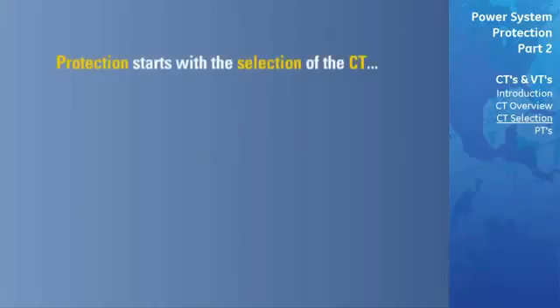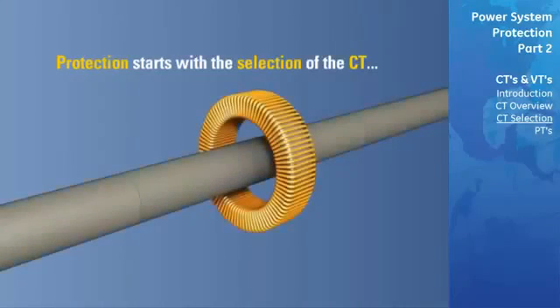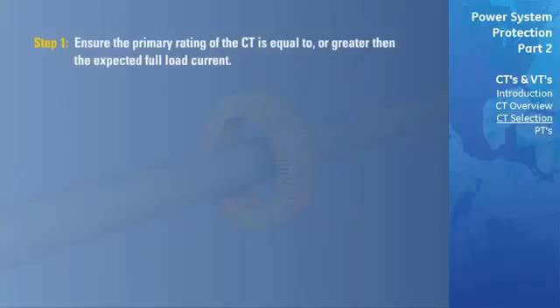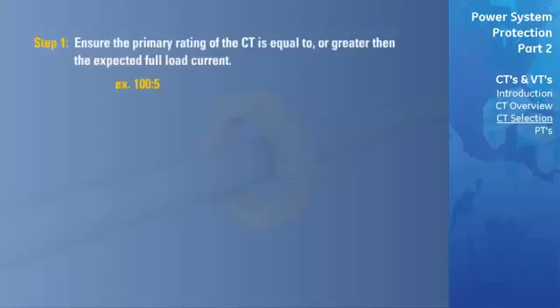Proper protection starts with the selection of current transformers. The following is a simple procedure that can be used to check whether or not there is the possibility of CT saturation. The first step is to ensure that the primary rating of the current transformers is equal to or greater than the expected full-load current. We can determine the primary rating of a CT by looking at its ratio. For a ratio of 100 to 5, a CT has a primary rating of 100, meaning that no more than 100 amps should be passed through the CT under normal operating conditions.